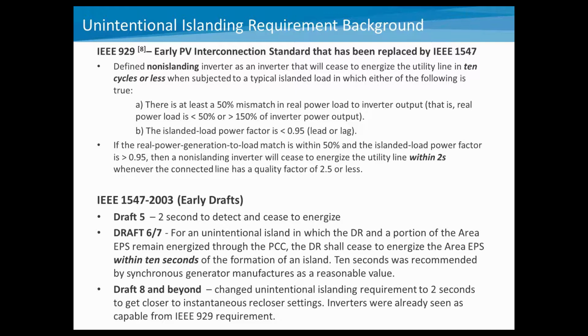2 seconds a lot of times is decided on as fast enough that people feel comfortable with it. But again, it's not fast enough to get inside instantaneous recloser settings. So if a recloser opens and then recloses, it's going to do that within the 2 second time frame. Inverters, especially if they're using an active anti-islanding technique, can usually meet the 2 seconds and oftentimes much quicker. But we'll get into some of the discussion on this later on.